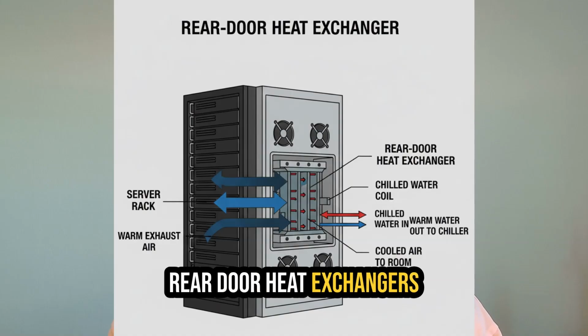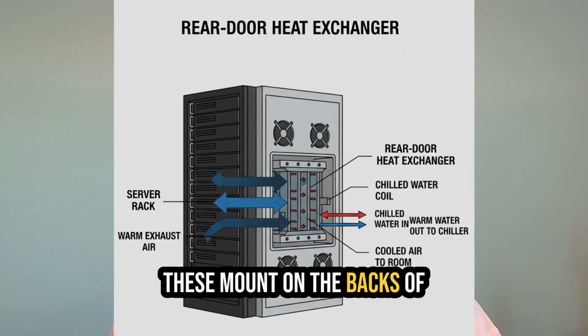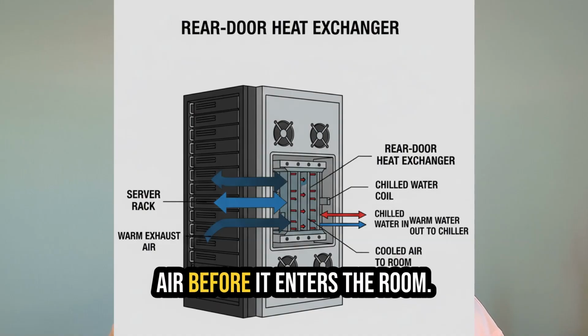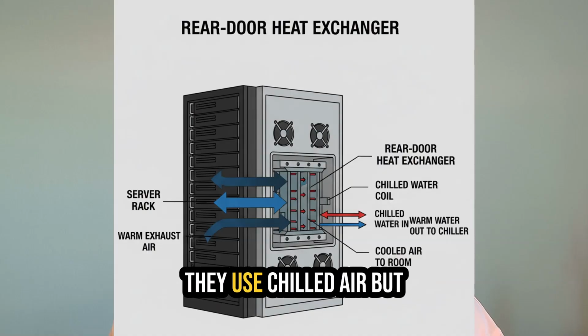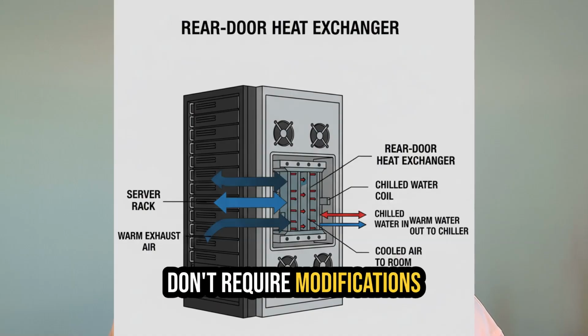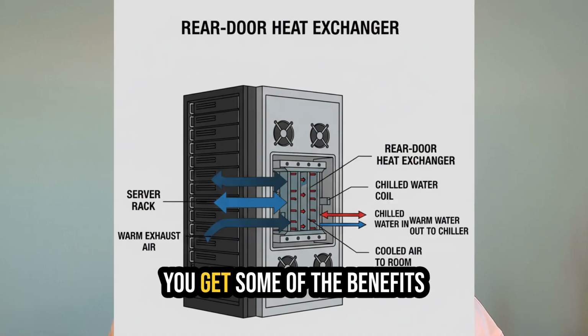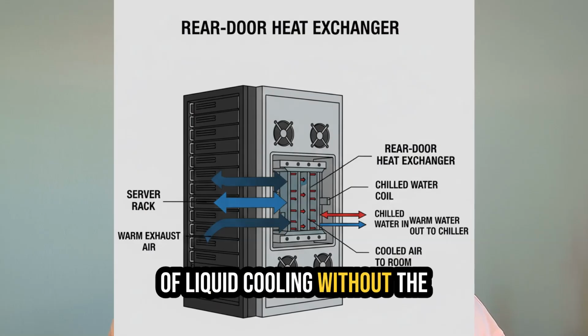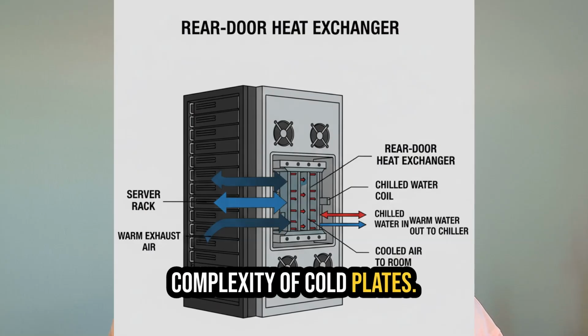Rear door heat exchangers offer a middle ground. These mount on the backs of server racks and cool exhaust air before it enters the room. They use chilled water but don't require modifications to the servers themselves. You get some of the benefits of liquid cooling without the complexity of cold plates.